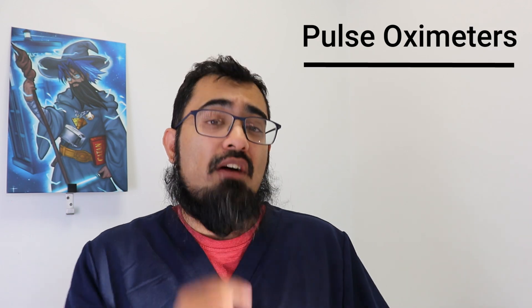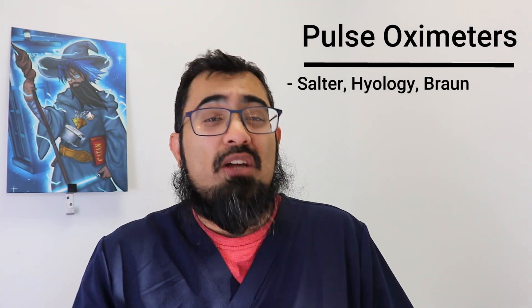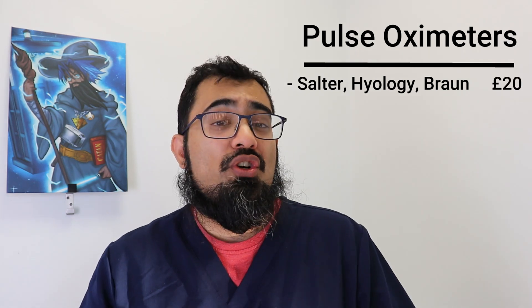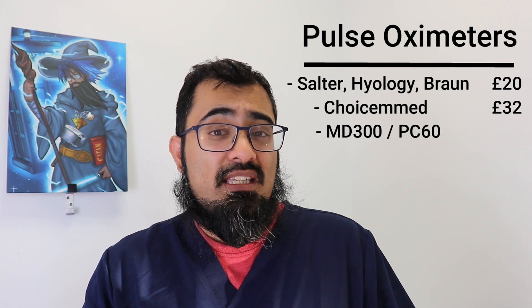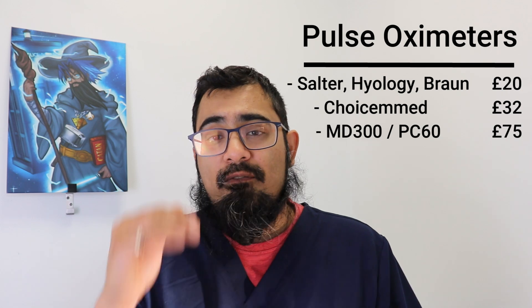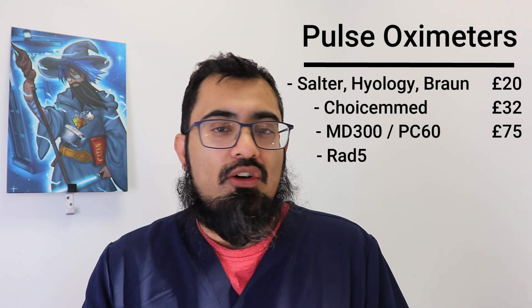For first class, consider the Rad 5 — an impressive piece of kit that lets you check SATS on a child all the way down to infant and neonate ages depending on attachments. However, this will set you back approximately £1,000 or more, so it's often something I recommend practices or hospitals keep rather than individual clinicians. To summarise: economy options like Salter, Braun, or Hyology are around £20; the Choicemmed is £32; the MD300 or PC60 around £70 to £80; and the Rad 5 potentially up to £1,000.